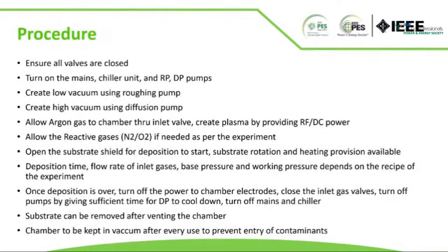This is a step-by-step procedure for operating the sputtering unit. Ensure all valves are closed. Turn on the mains, chiller unit, RP and DP pumps. Create low vacuum using the roughing pump. Create high vacuum using the diffusion pump. Allow argon gas into the chamber through the inlet valve. Create plasma by providing RF or DC power. Allow the reactive gases if needed as per the experiment. Open the substrate shield for deposition to start.